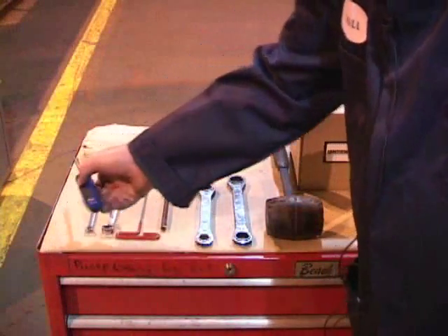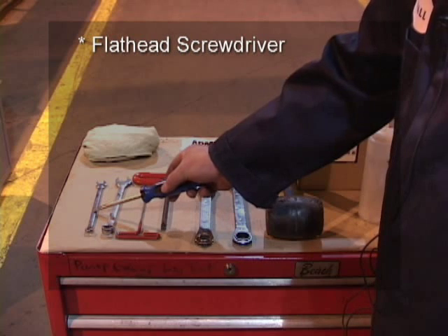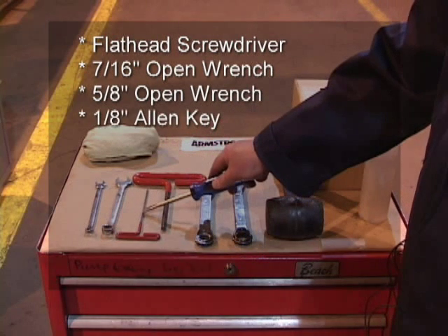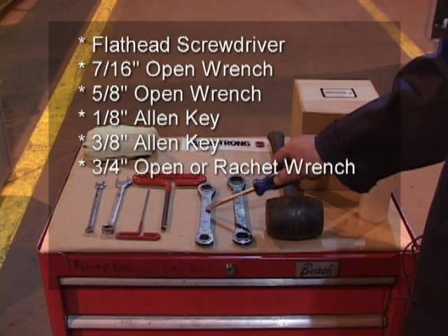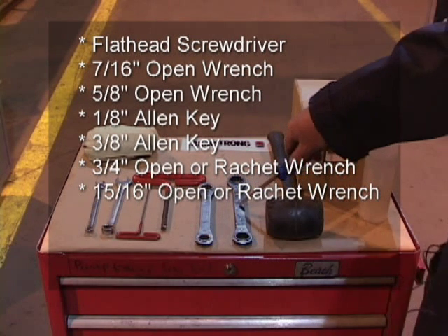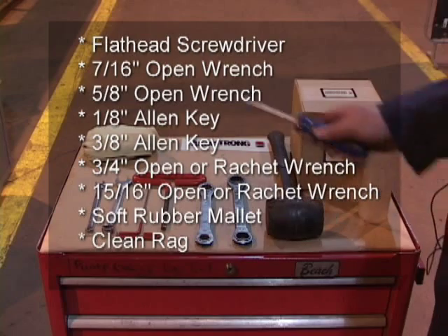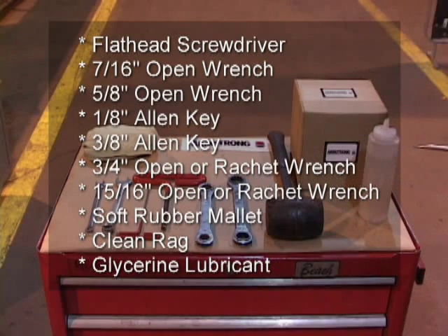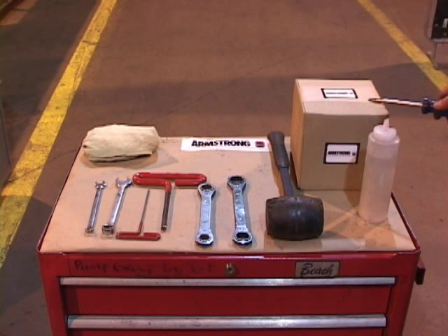Here are the tools we are going to need today to repair the mechanical seal in this pump: a flathead screwdriver, a 7/16-inch open wrench, a 5/8-inch open wrench, a 1/8-inch Allen key, a 3/8-inch Allen key, a 3/4-inch open or ratchet wrench, a 15/16-inch open or ratchet wrench, a soft rubber mallet, a clean rag, lubrication for the shaft and seal — typically a non-petroleum-based product like glycerin — and the replacement Armstrong 2-5/8-inch mechanical seal.